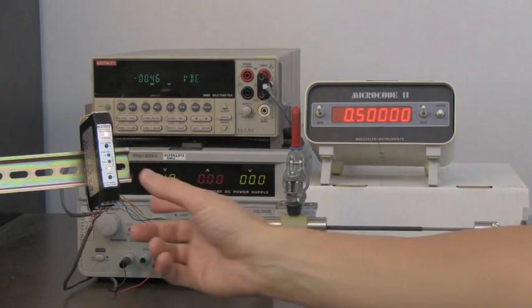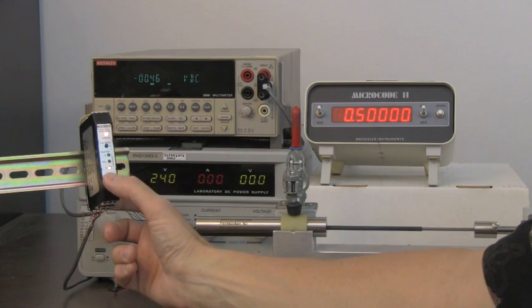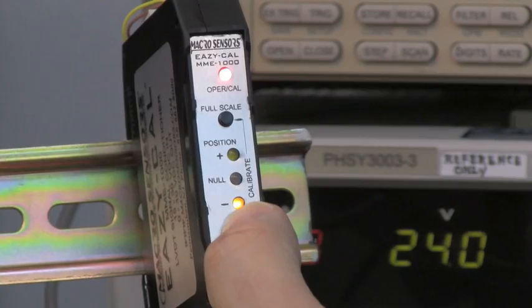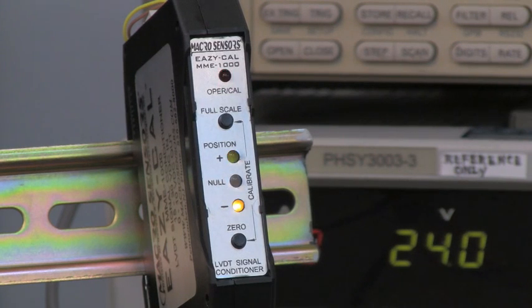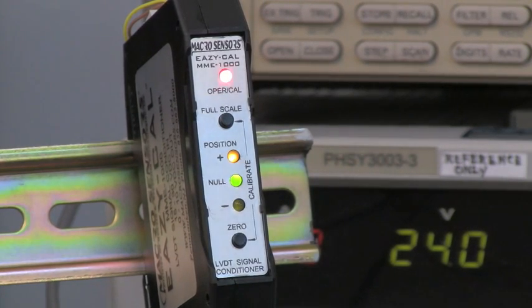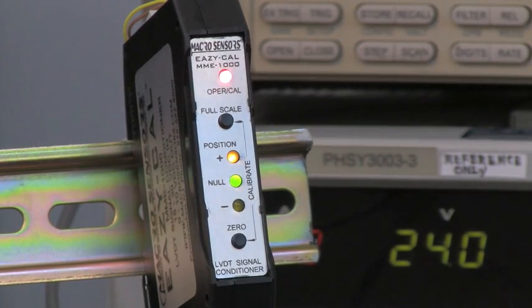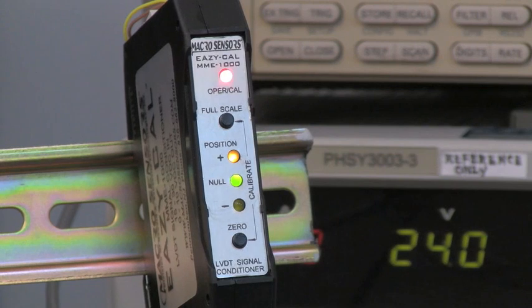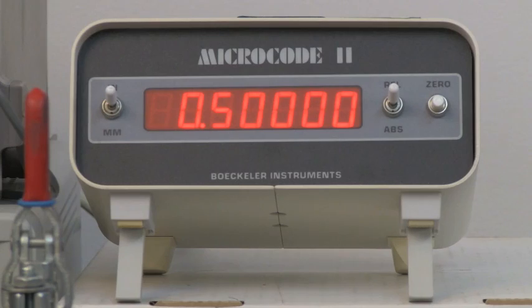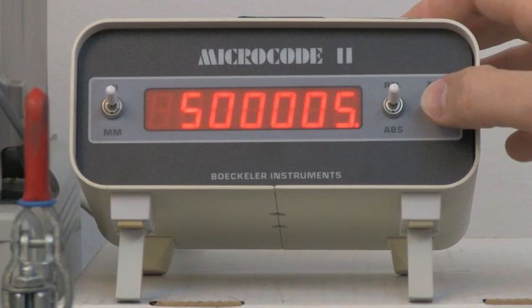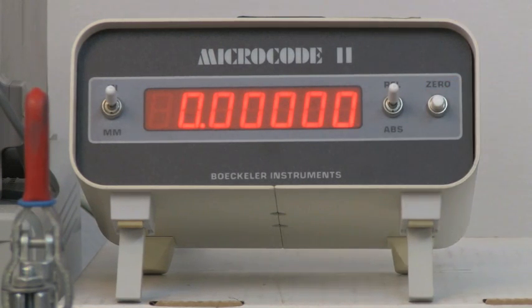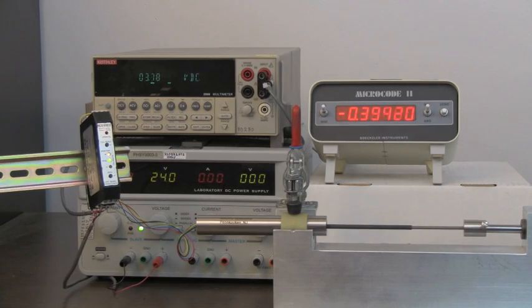Next, we enter the 0 calibration point into the EAZY-CAL by momentarily pressing the 0 push button. The 3 positional indicator lights on the front panel will then briefly sequence, providing positive feedback that the 0 point has been stored. The positive position LED lamp will then illuminate. We now reset the digital micrometer readout to 0. Next, we displace the LVDT by plus 1.0 inches.